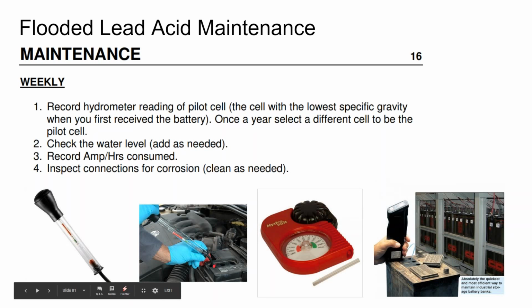But then at night, if you use the same 7 kilowatts of power coming out of a very small battery bank, then you get into that below C5. You get into that rate where, 7 kilowatts on 20 kilowatt hours, that's a C3 rate. 10 kilowatt hours on 7 kilowatts, that's a C1.5. And most of that electricity is just going to be burned up as heat.